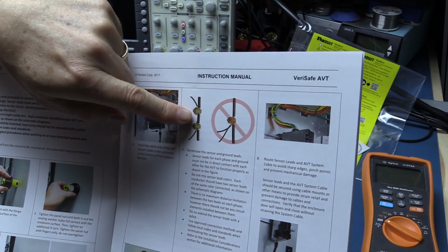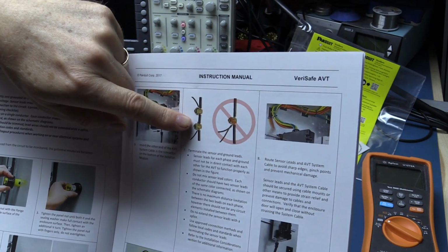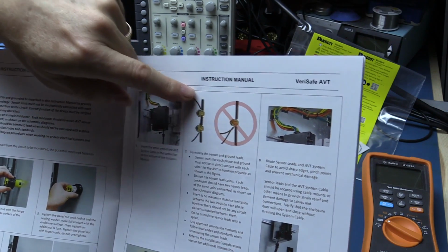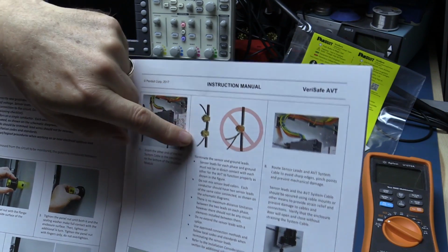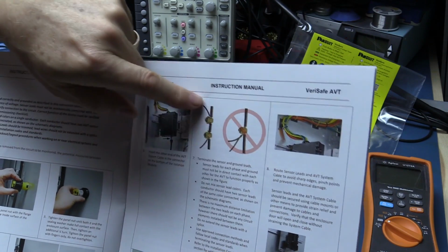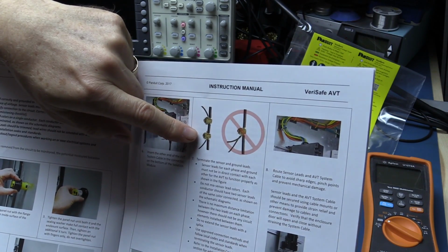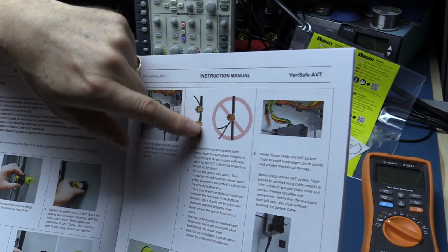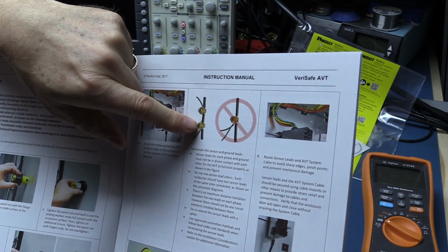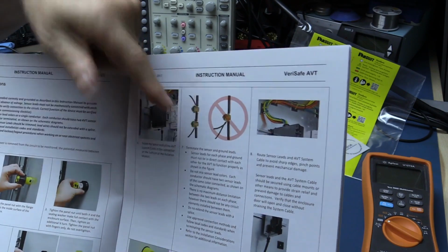The chances of both these wires coming out is very, very slim. Secondly, the sensing wires actually sense between themselves to make sure there's continuity between the 2 sensors of each same color. The benefit is it makes sure it's also measuring that the wire it's connected to is intact. So it's lots of belts and braces type things.